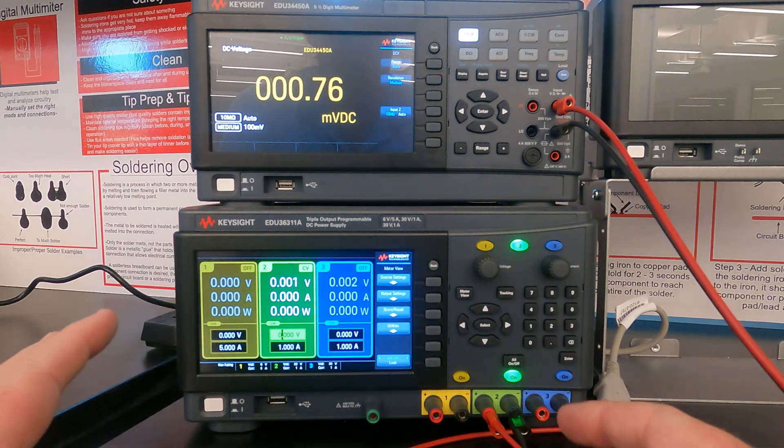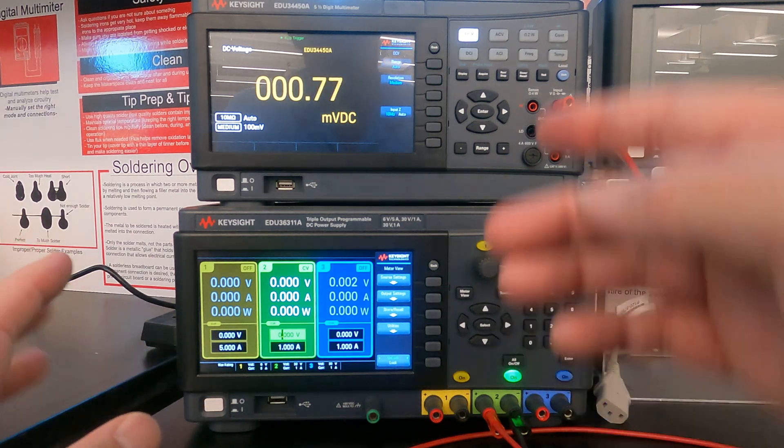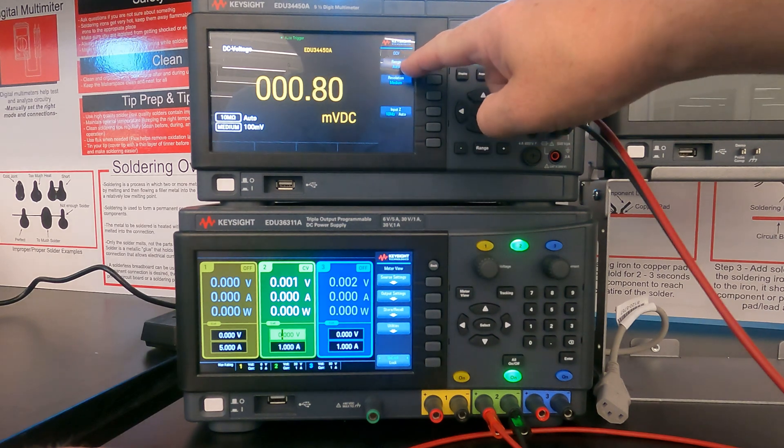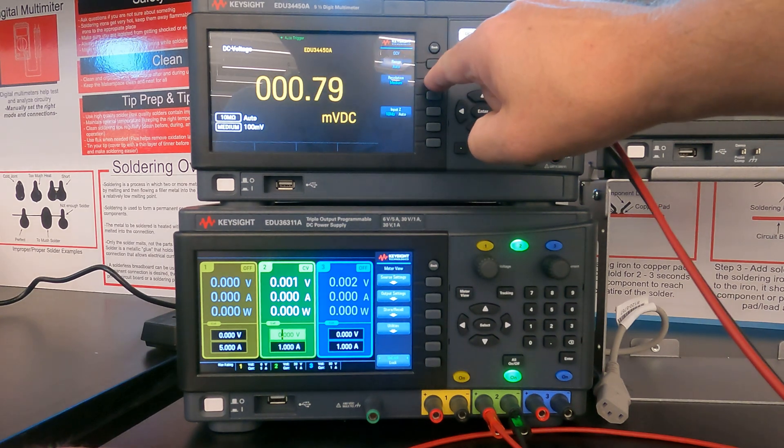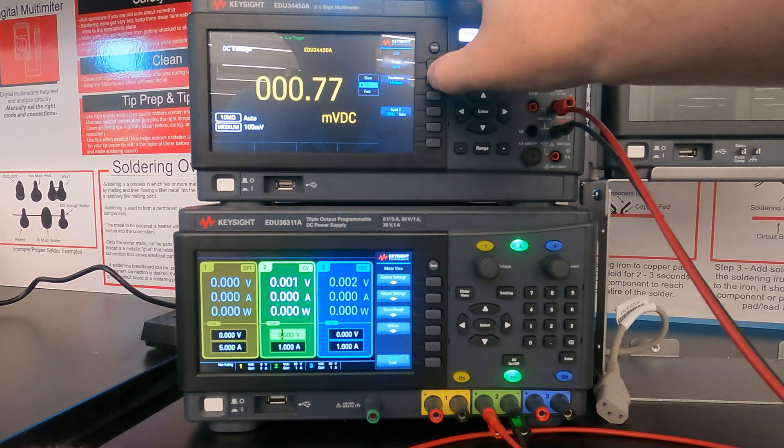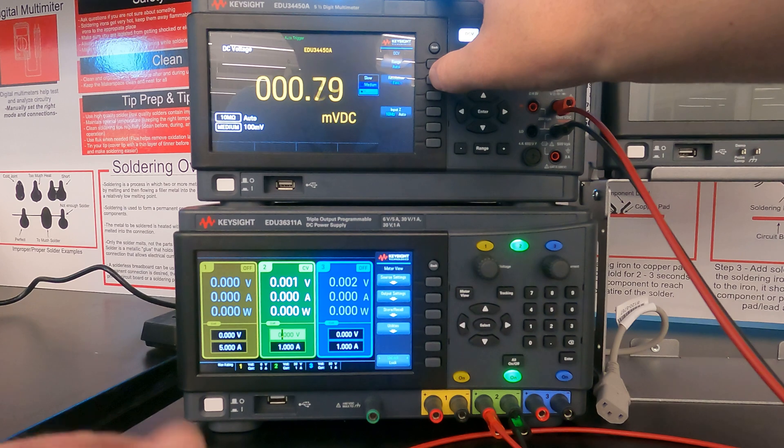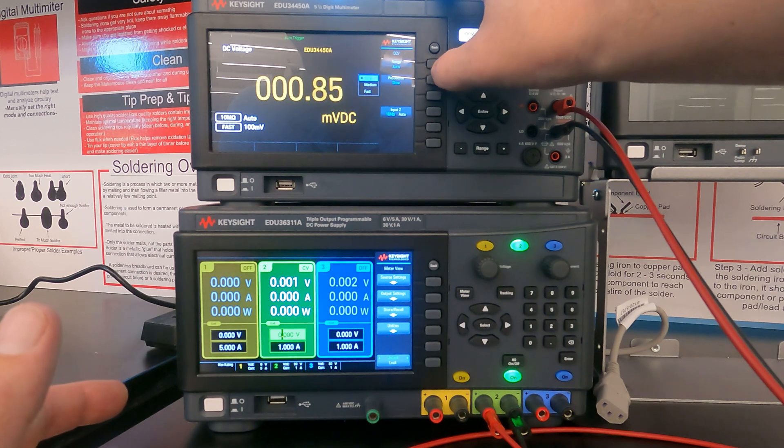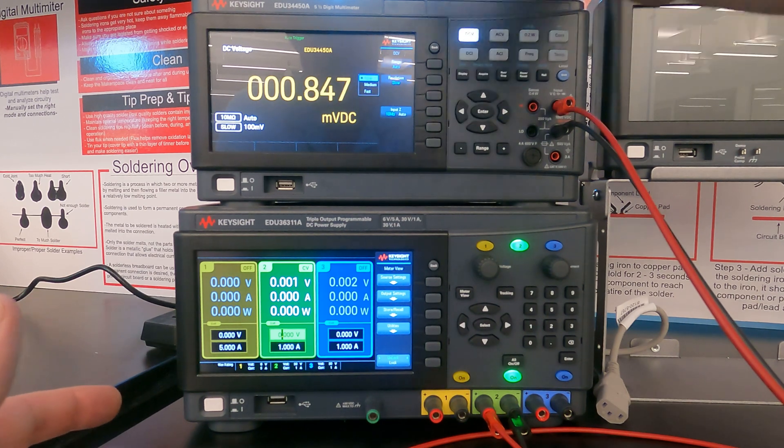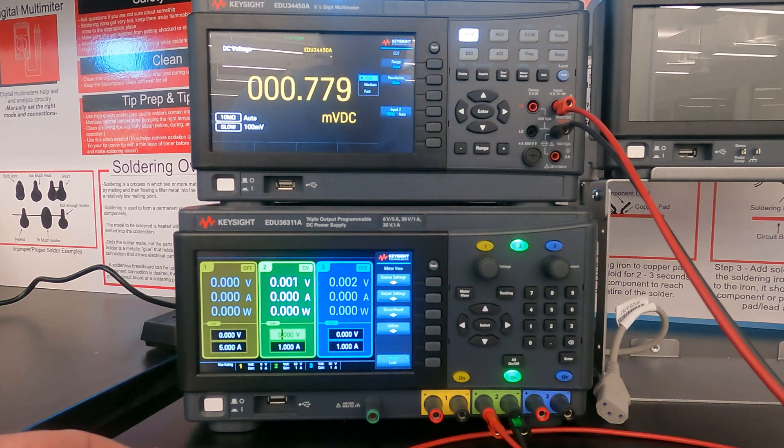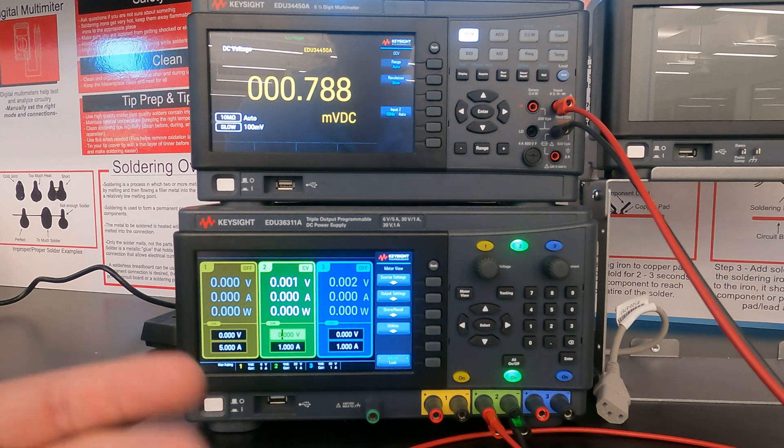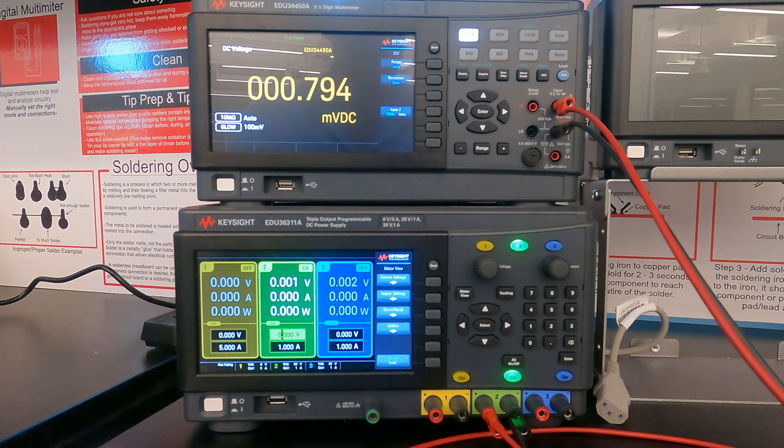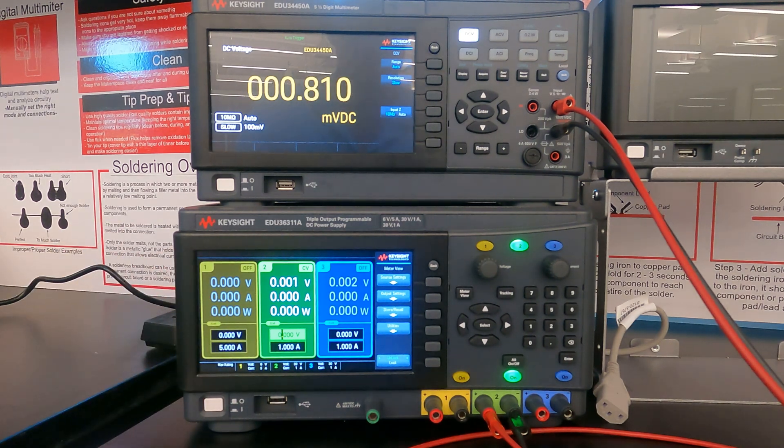Now we want our range in auto and our resolution here, we can have at any the, you can switch between it by pressing this button multiple times. Slow will be the most accurate, but fast will give you the readings the quickest. If you're making a bunch of readings, maybe you want that.